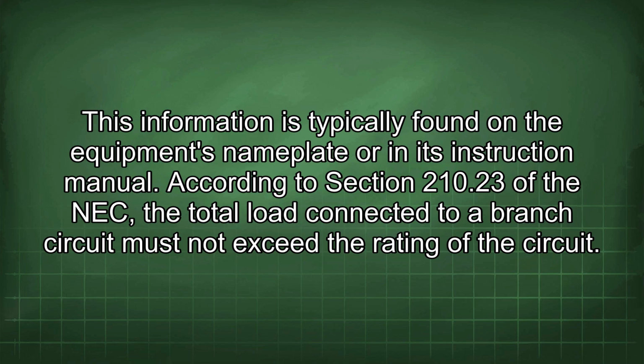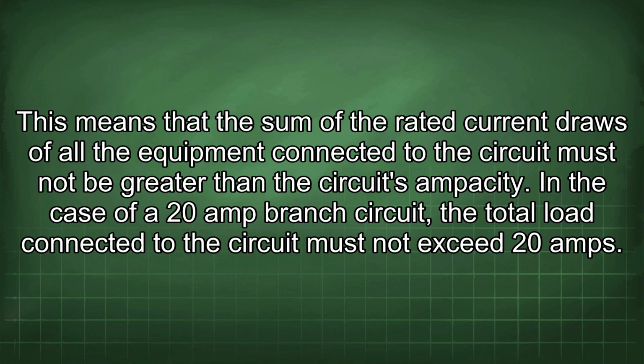According to Section 210.23 of the NEC, the total load connected to a branch circuit must not exceed the rating of the circuit. This means that the sum of the rated current draws of all the equipment connected to the circuit must not be greater than the circuit's ampacity. In the case of a 20 amp branch circuit, the total load connected to the circuit must not exceed 20 amps.